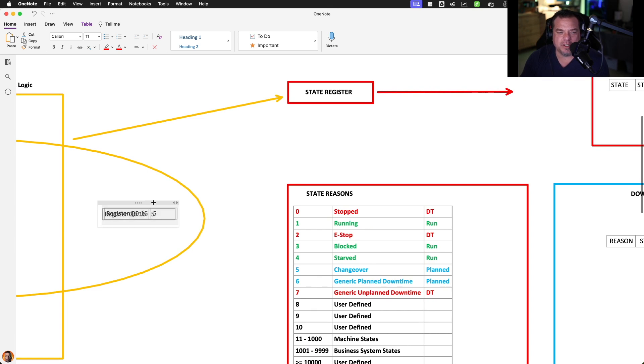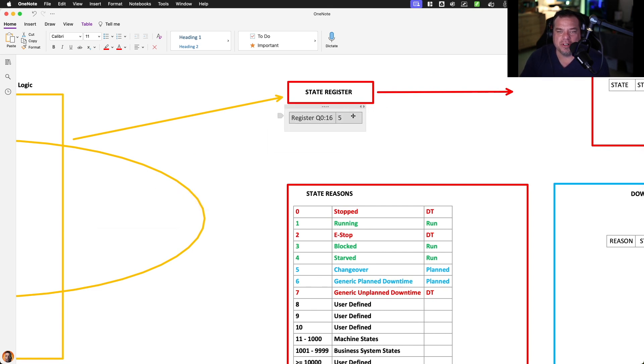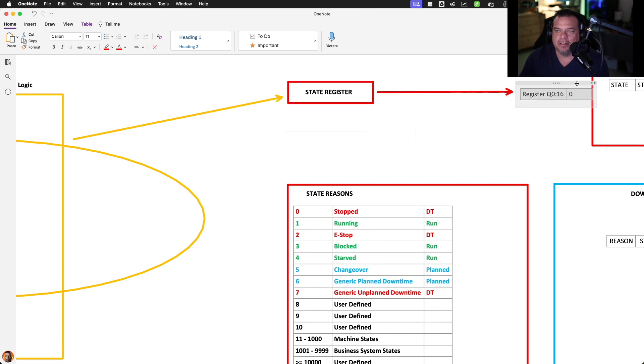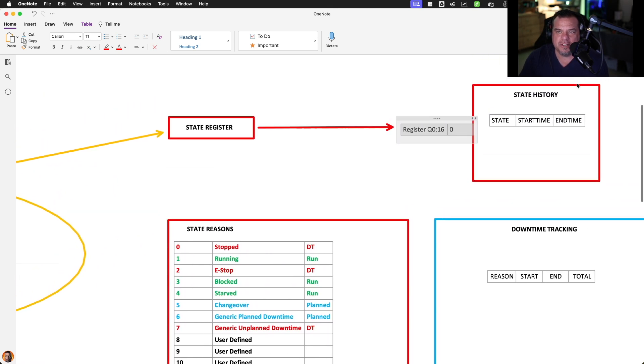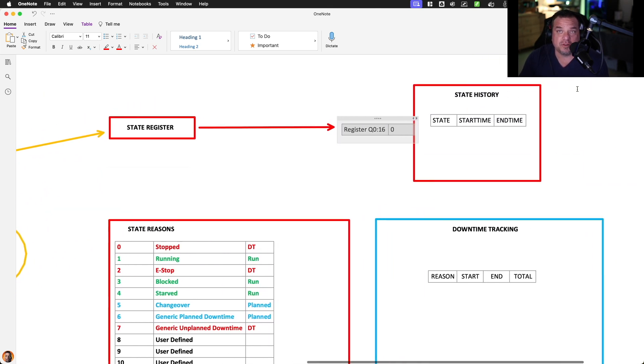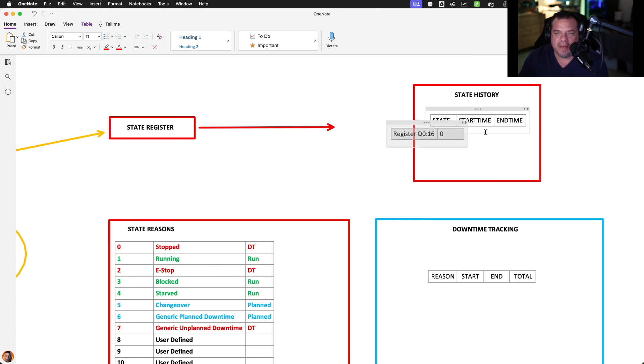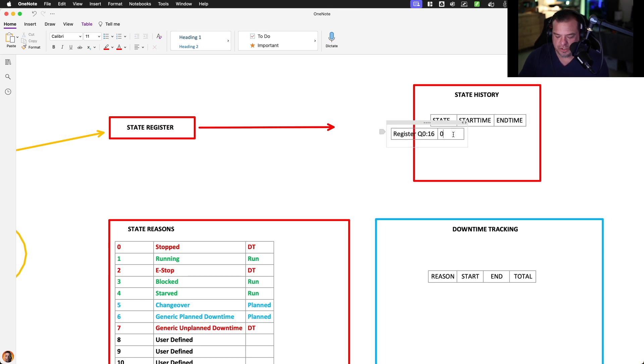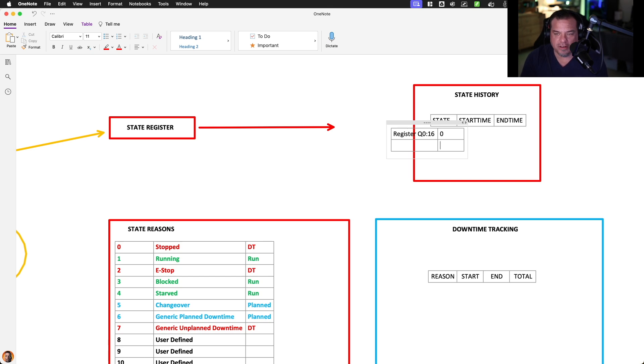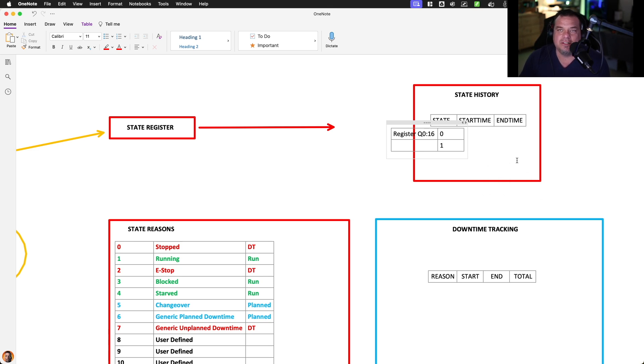What do we do when we have the status register? Once we have the status register, every time it changes, we're going to insert a record into a state history table. This is tracking state. We're going to insert a record into state history table. So we're going to end up with the state and then a start time, and there will be no end time while it's in the current state. And then when it changes, we will insert another record. So then it will be 1, and then the 0 will have a start time and an end time, and the 1 will have a start time. And as the register changes, we're storing that in the state history table.